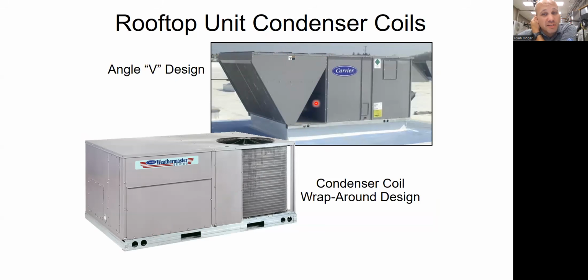I'm just saying that because it means that what happens on these rooftop units sitting on this curb right here, and when we go to replace this, we want something new that fits on the same curb, because then it's a really easy swap. Disconnect the gas and electric, pick the unit up, put the new unit down, connect the gas and electric. It's like a 2-hour project. If it doesn't line up with the old curb and the old ductwork, then it becomes a much more involved project, involves the roofing company and so forth. So they really want them to fit on the same spot.